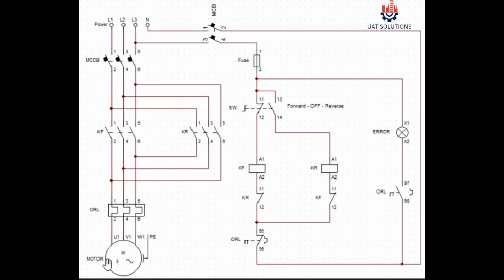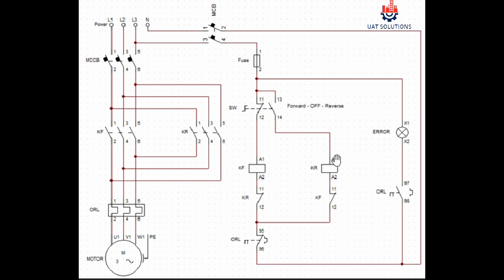To run the motor in reverse function, selector switch will have to be turned to the reverse side, which will result in closing point 13 and 14, and phase will be supplied at coil terminal A1 of contactor KR.